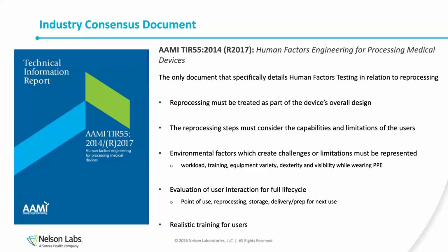And then again, just being aware of the full cycle. So typically, if we're talking healthcare setting, there's a point of use treatment for a reusable device. Then there's the transport to SPD for reprocessing. Then there's the prep and storage for that. Then the delivery and prep for it being used again. So there really is a lot of steps that you have to think about through the whole human factors test.